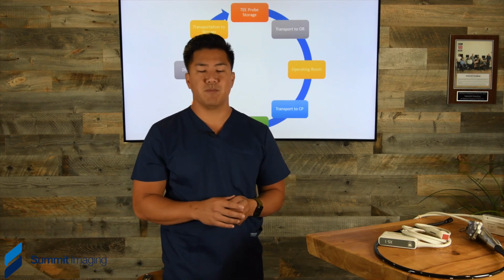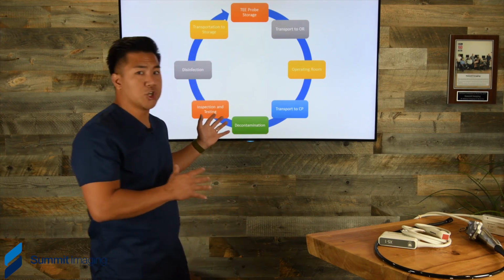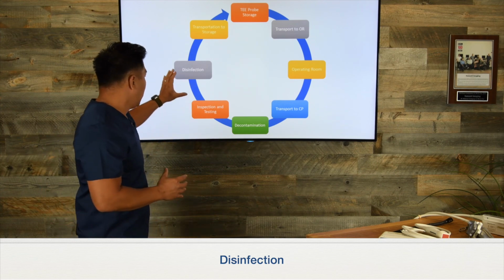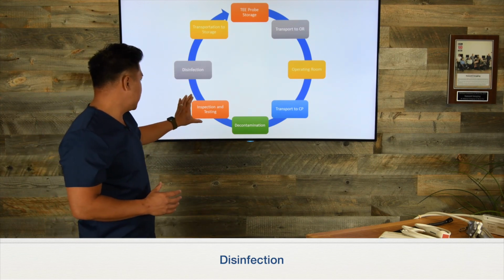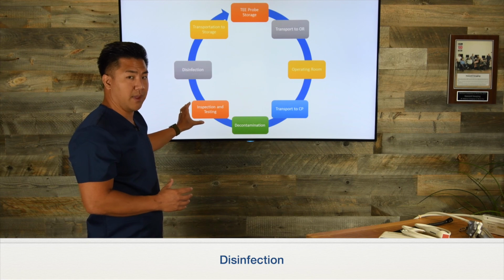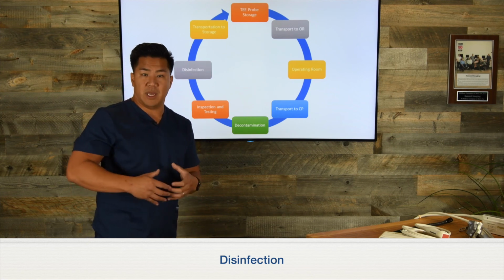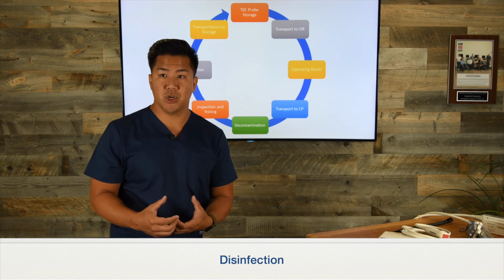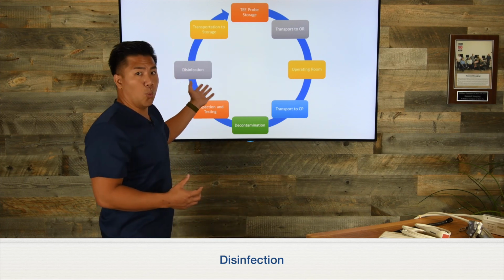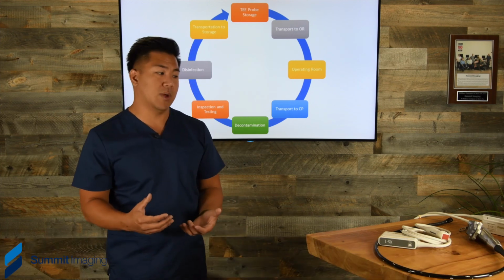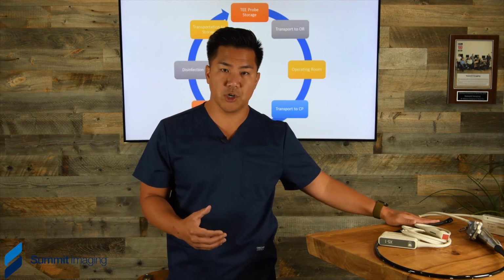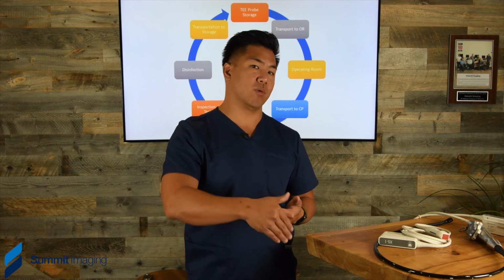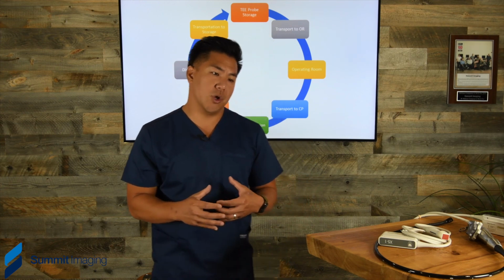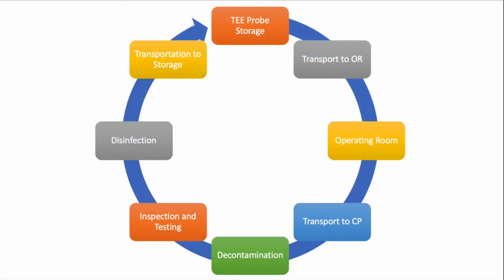Reference your service manual. But during the disinfection process, we want to highlight the inspection and testing phase, because if there are any punctures, you don't want the disinfecting fluid to go through these small micro punctures into the internals of your transducer.